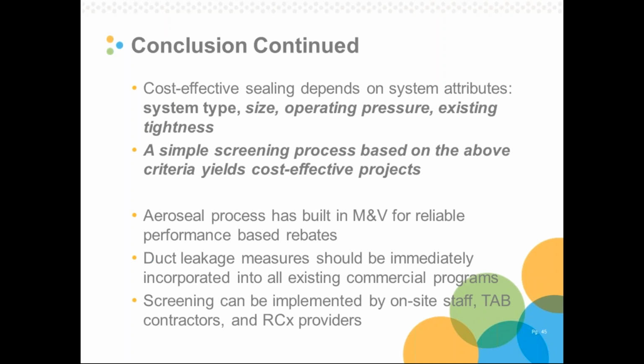Cost-effective sealing depends on system attributes. We found that if we select systems based on type, size, operating pressure, and existing tightness, we can successfully find good cost savings opportunities. This simple screening approach can be applied widely starting now. The Aeroseal process is built-in M&V for reliable performance based rebates. I will say here that 3 of our 5 pilot sites ended up independently pursuing custom rebates with their utilities, and that, to my knowledge, was a fairly painless process for all of them. Duct leakage measurements should be immediately incorporated into all existing commercial programs, and screening efforts should be implemented starting right now after this talk.